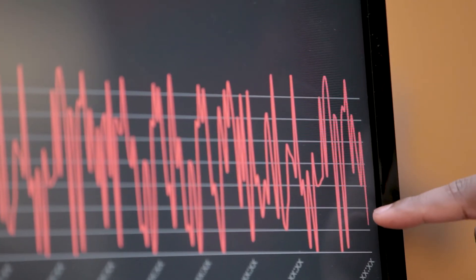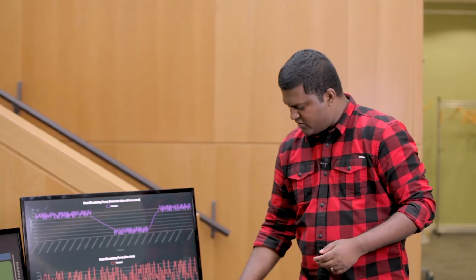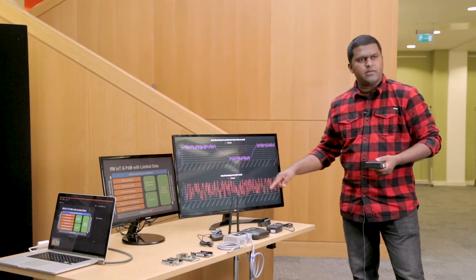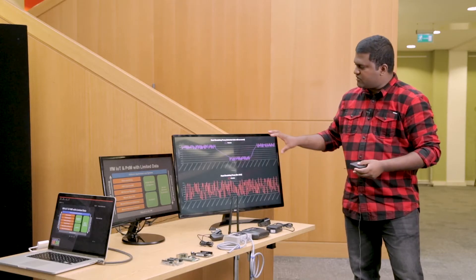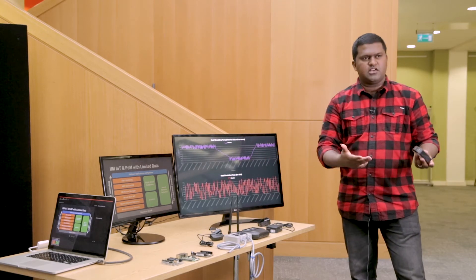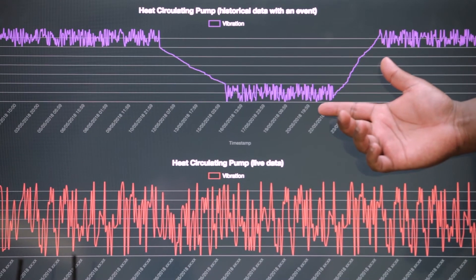Here you can see live data coming from the pumps using this sensor attached on top of a pump. We're capturing that real-time data here, and this shows historical data. We actually managed to capture a boiler failure last month from this trend.